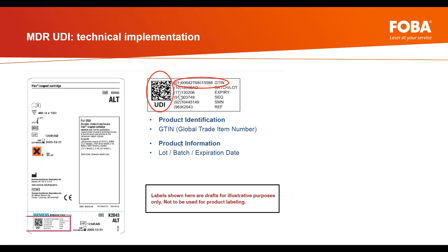So what is also important, as you see here in the example of our Marcus Designer, you maybe have seen it before, is that we have 3 levels, and it's very important to have 3 levels of the software. We have the highest level with the login data. It's the administrator. That's where you define the laser power, the scan speed, the pulse rate. You see it very small down here in this column. So that's defined by one validated process, and the rights are given to the head of production, quality manager, whoever is responsible. At the designer level, you can add a CE mark, a barcode, a human-readable UDI code. It's all in the software.